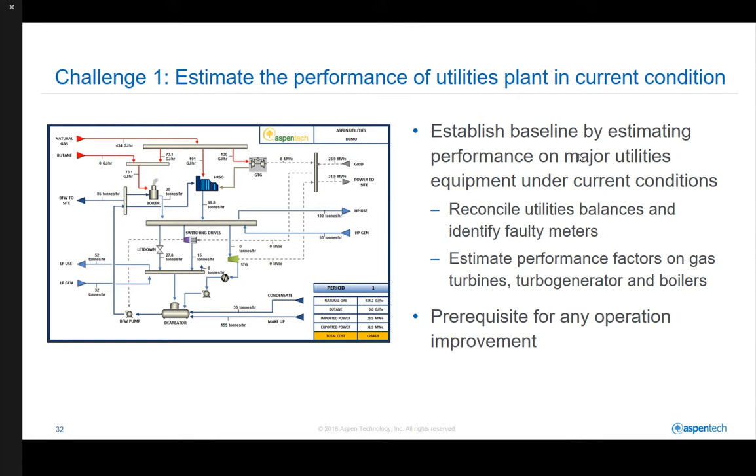Three operation challenges are faced by the utilities plant operators in this demoed process. Firstly, utilities plant operators and process engineers need to estimate the true performance of key equipment such as gas turbines, steam boilers, and steam turbines under current operating conditions. The work involves reconciling the utilities balance and identifying the faulty meters. This will help to establish the baseline operation scenario, which is prerequisite for any future operation improvement.